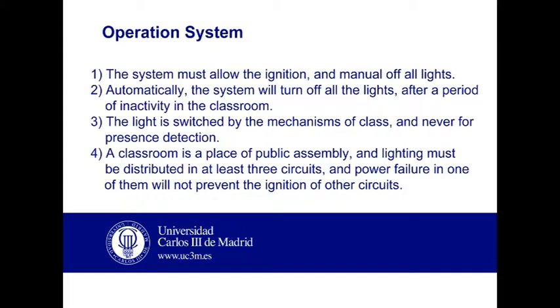3. The light is switched by the mechanisms of class and never by presence detection. 4. A classroom is a place of public assembly, and lighting must be distributed in at least three circuits. Power failure in one of them will not prevent the ignition of other circuits.